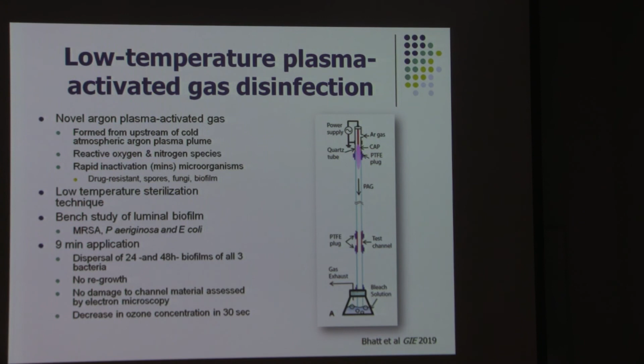This is a study from this year at GIE looking at a novel argon plasma activated gas. That is a low temperature sterilization technique. In the bench study, of luminal biofilm of all the superbugs here, after 9 minutes of application, there was a dispersal of both 24-hour and 48-hour biofilms of all 3 bacteria. There were no regrowths. And what is more important, there was no damage to channel material, and it did not require a long aeration process. There was a decrease in ozone concentration in 30 seconds. So this is something to look forward to.